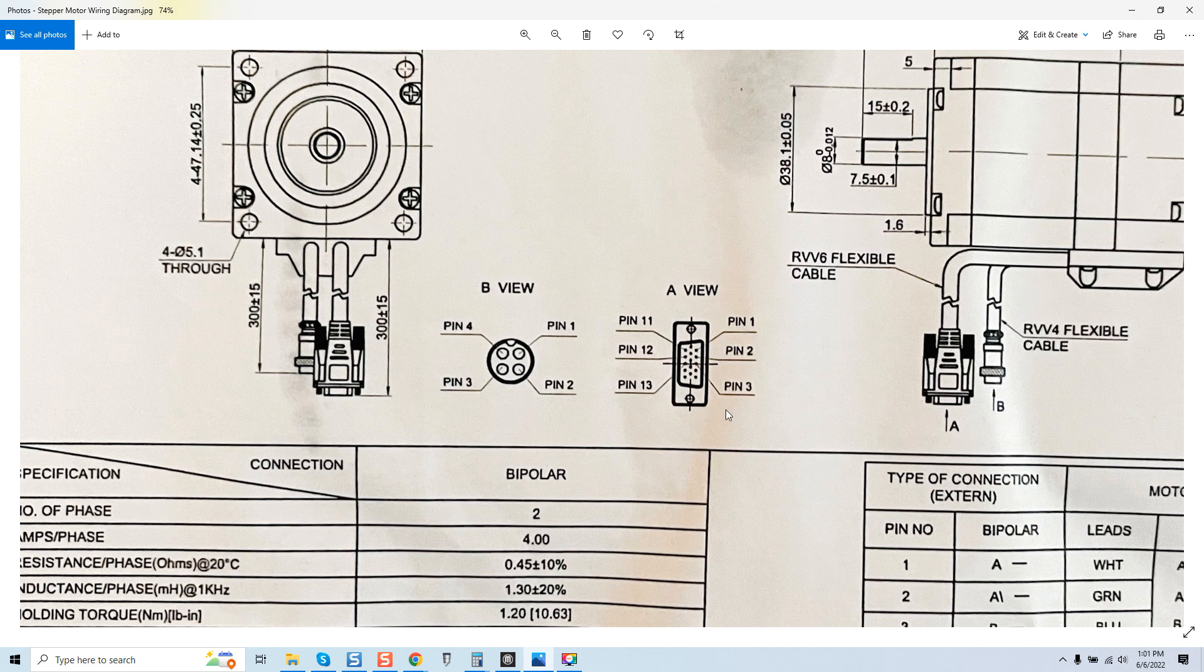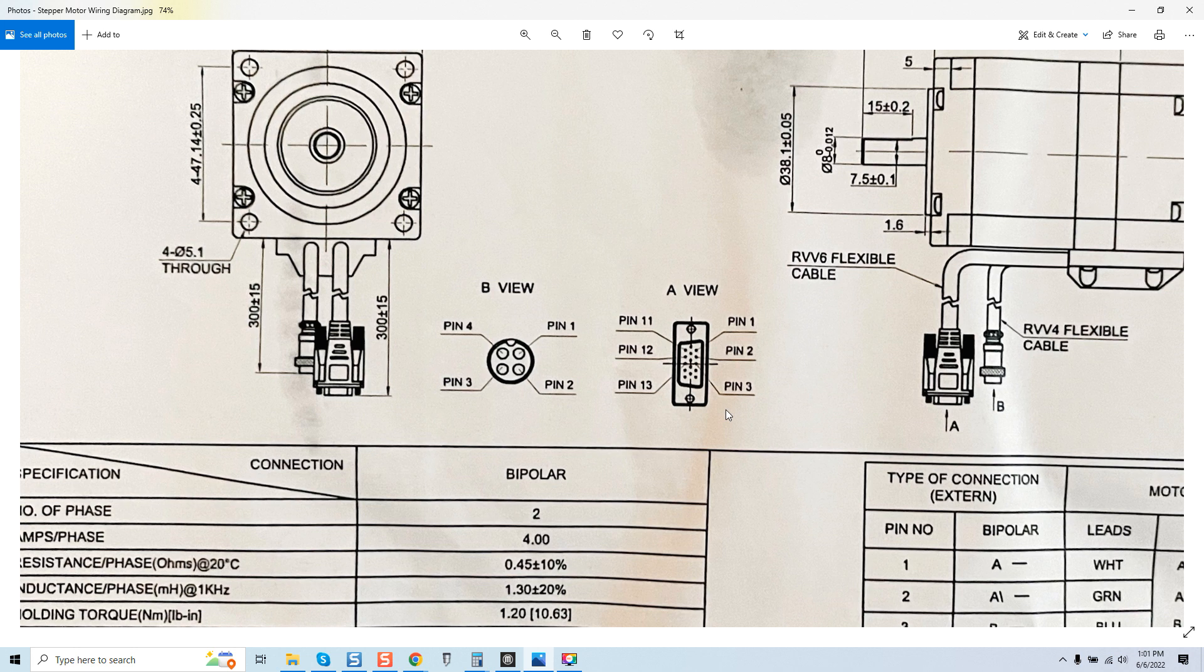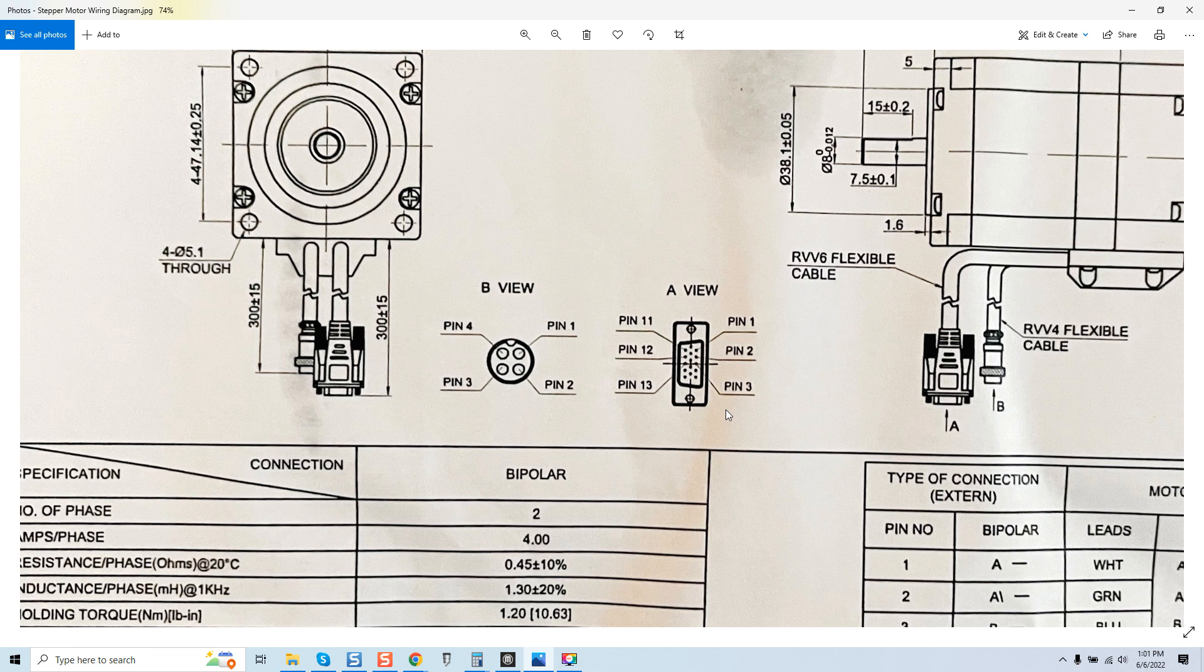How long can you go with an encoder cable? Well that's a good question. I get asked that a lot. I would not go past 15 feet in length mainly because you're dealing with very low voltage signals. So again keep that in mind that it's not an indefinite cable run. You know some guys want to go 30, 35 feet, I've heard of in excess of 40 feet and that's getting ridiculous.